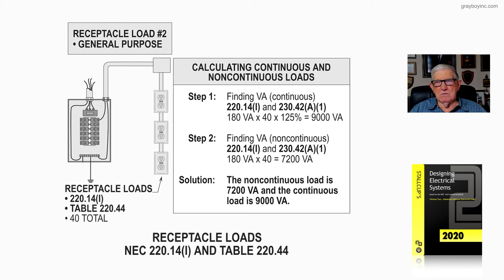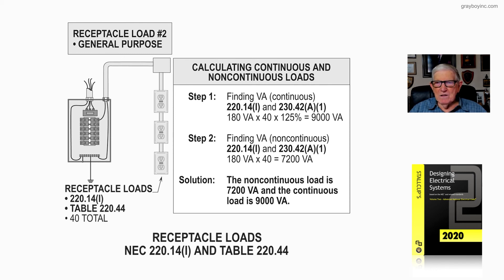If they were non-continuous, then we'd have 180 VA times 40, which gives us 7,200 volt-amps because they are used non-continuously. But we still haven't exceeded 10,000, so table 220.44 cannot be applied here. So the solution is: the non-continuous load of the receptacles is 7,200 VA, and the continuous load of the receptacles is 9,000 VA. That's exactly what illustration 23-9 is illustrating to the user of the NEC.